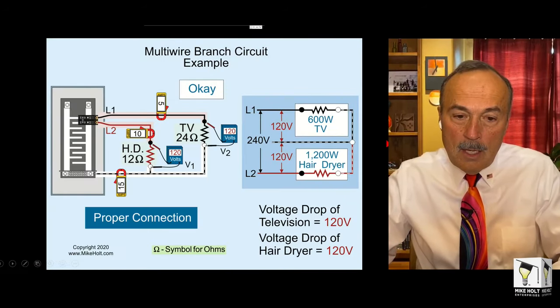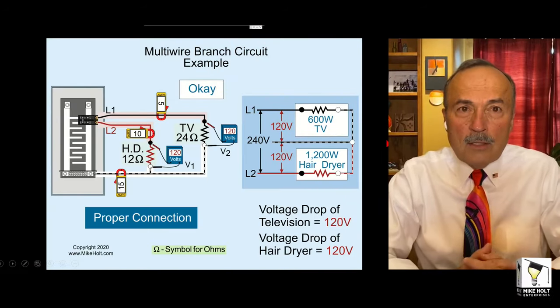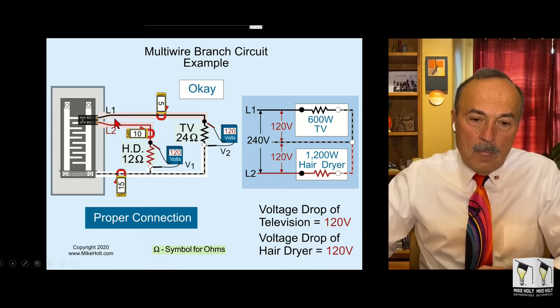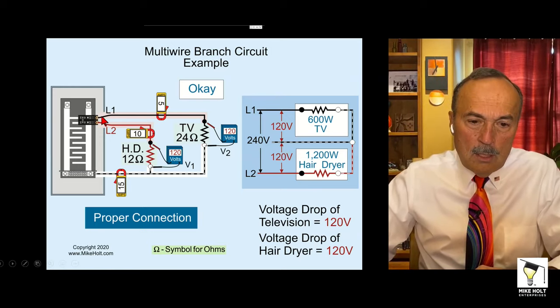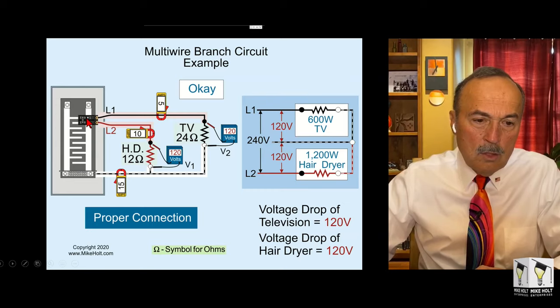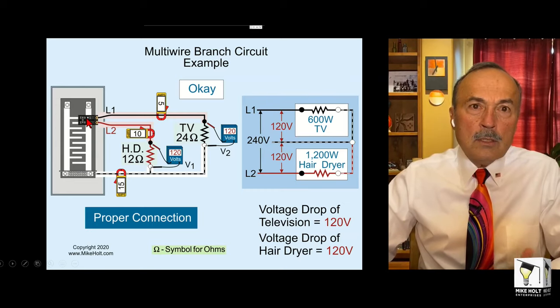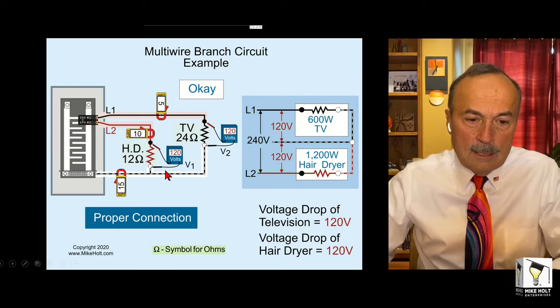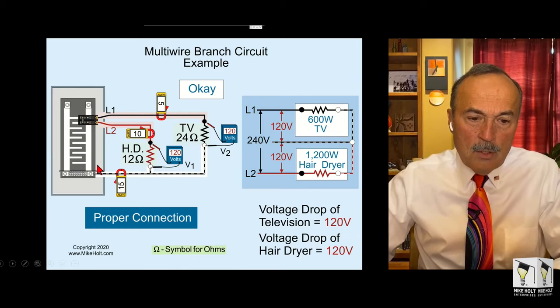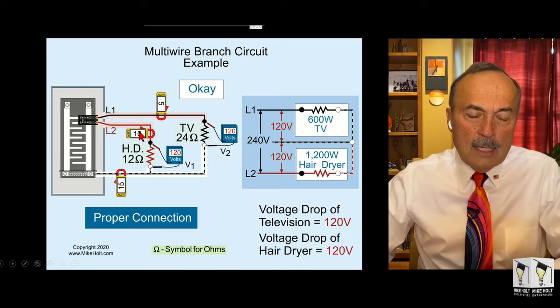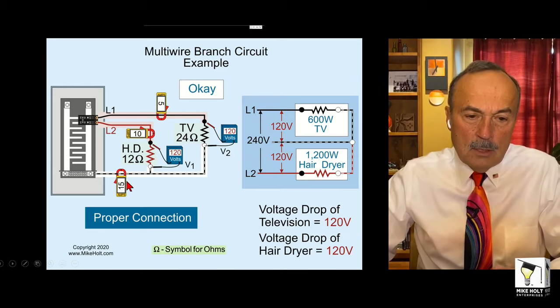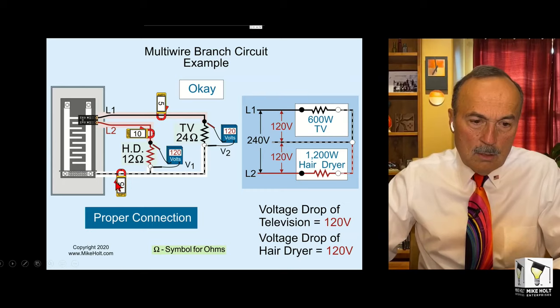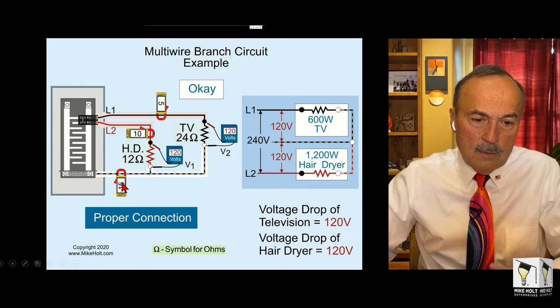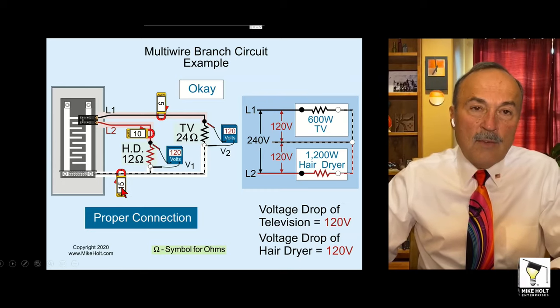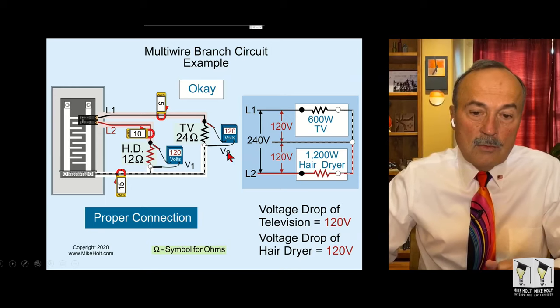Sorry about that. Now let's review multi-wire branch circuits, which we reviewed in the past. Here's line one, here's line two, there's a two-pole breaker, or there's two single-pole breakers with handle ties, and then you have your common neutral multi-wire branch circuit. Let's say line one draws 5 amps, line two draws 10 amps. Oh, this is wrong here. So unfortunately, that was wrong. That should have been 5 amps on that graphic. So I apologize for that.